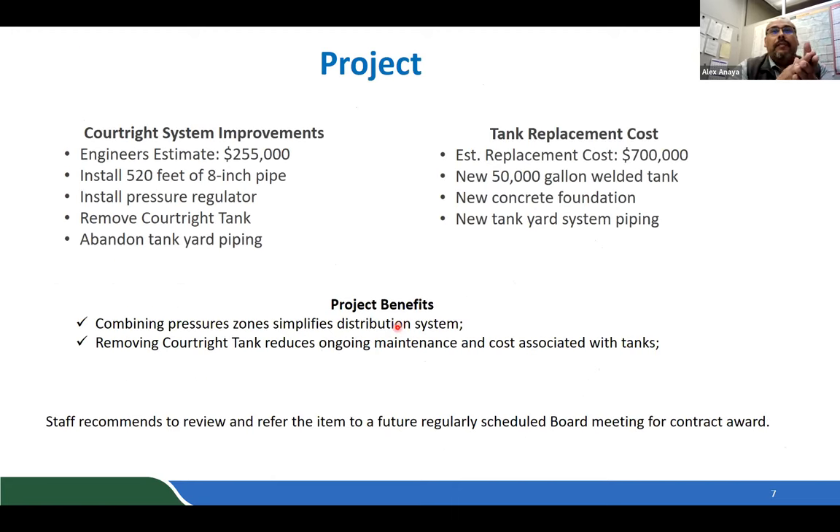The Courtright System Project is estimated at $255,000 to install 520 feet of 8-inch pipe and a pressure regulator valve, and to abandon the tank yard piping. For comparison, replacing the tank would cost around $700,000 for a new 50,000-gallon welded tank with concrete foundation, tank yard piping, and drainage improvements. The project combines two pressure zones into one, simplifying the distribution system and eliminating future maintenance and tank coating costs.